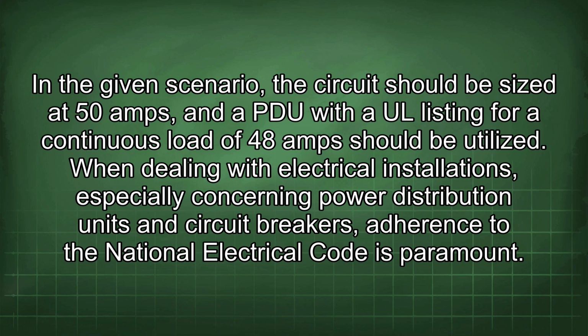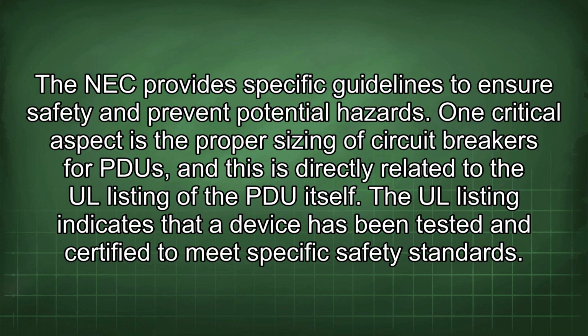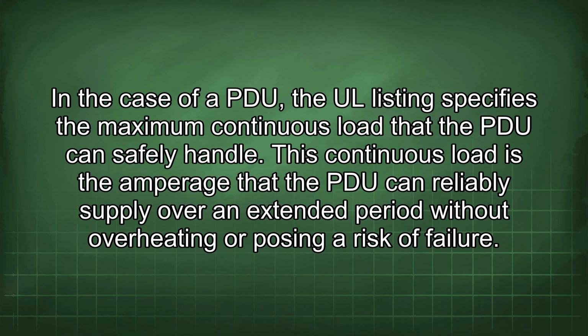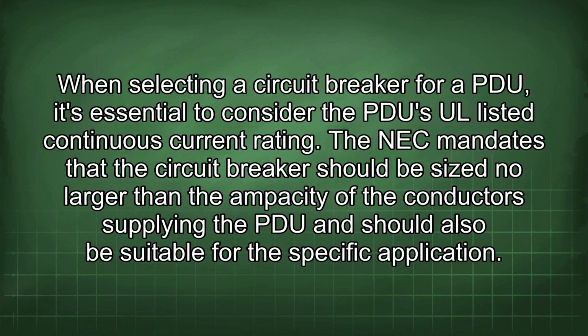When dealing with electrical installations, especially concerning power distribution units and circuit breakers, adherence to the National Electrical Code is paramount. The NEC provides specific guidelines to ensure safety and prevent potential hazards. One critical aspect is the proper sizing of circuit breakers for a PDU, and this is directly related to the UL listing of the PDU itself. The UL listing indicates that a device has been tested and certified to meet specific safety standards. In the case of a PDU, the UL listing specifies the maximum continuous load that the PDU can safely handle. This continuous load is the amperage that the PDU can reliably supply over an extended period without overheating or posing a risk of failure.